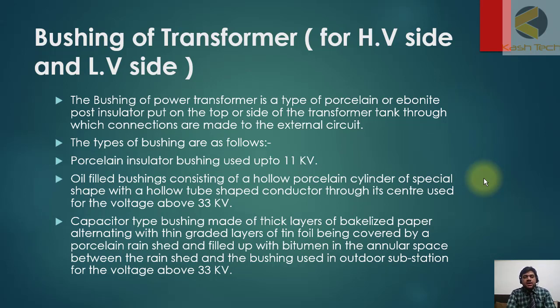The types of bushings are as follows: Number one, porcelain insulator bushing used up to 11 kV. Oil-filled bushing consisting of a hollow porcelain cylinder of special shape with a hollow tube shaped conductor through its center, used for voltages above 33 kV.